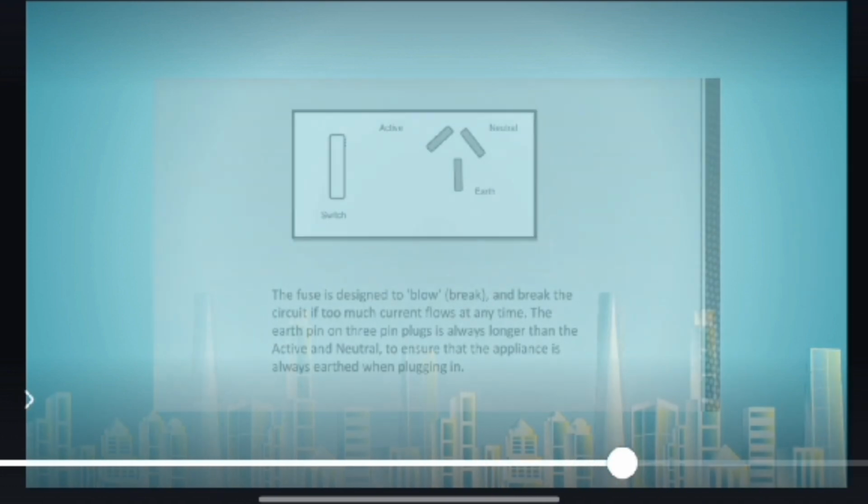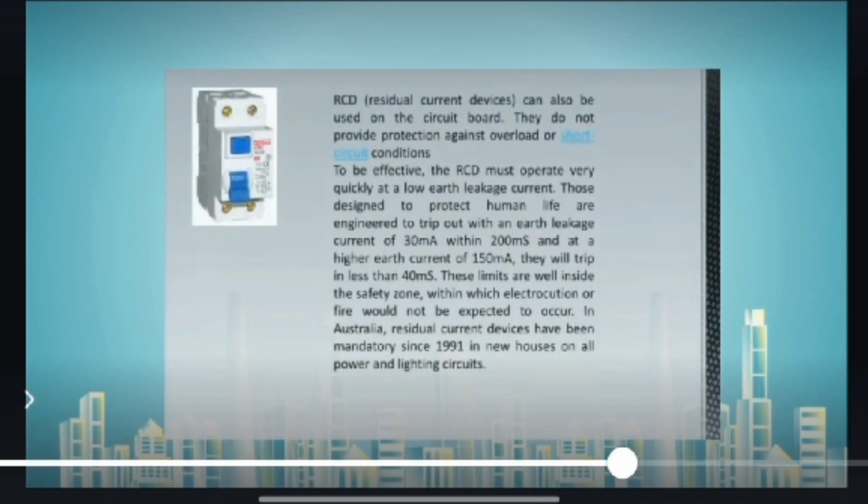An RCD can also be used on a circuit board. They do not provide protection against overload or short circuit conditions. To be effective, the RCD must operate very quickly at a low earth leakage current.